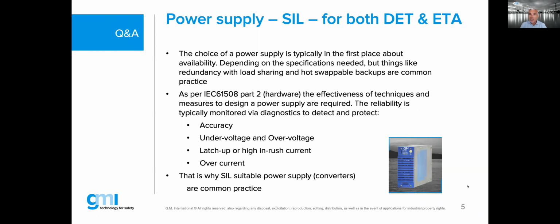Let's talk about the energized to activate. Let's also talk about the de-energized to trip, as we showed in the webinar earlier, in the earlier slides. Now, the choice of the power supply is typically in the first place all about availability. Is my power supply available? Is it accurate? As we said already before, specific for the 61508, the quality design of such a unit, which is shown here in this picture of a GMI power supply, is measured on the measurements from the 61508 part 2, which is the hardware section. And we call this the effectiveness, or the rigorousness, or the quality of the hardware design. And those techniques are used to measure how well the power is being provided.